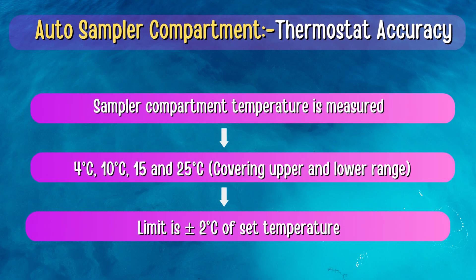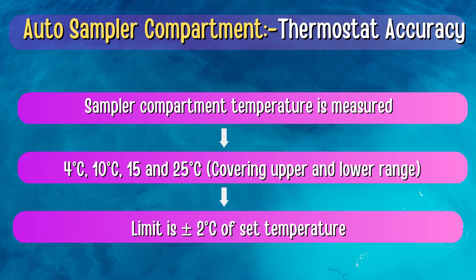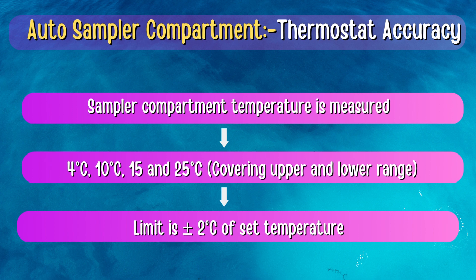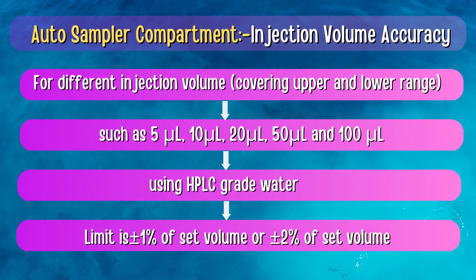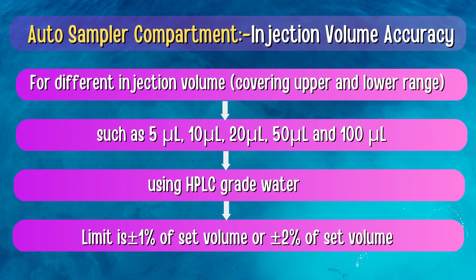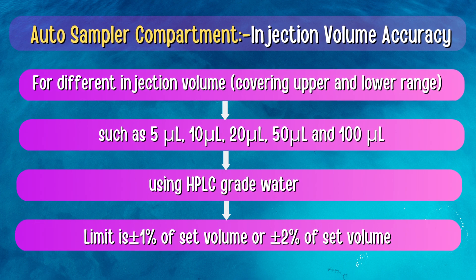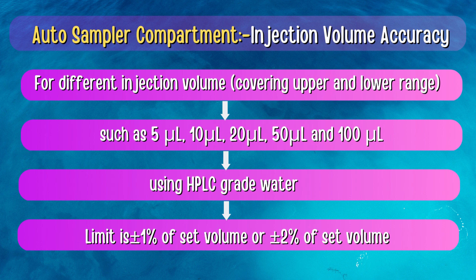For the Auto Sampler Compartment, Thermostat Accuracy is performed by measuring the sampler compartment temperature at 4°C, 10°C, 15°C, and 25°C. The limit is ±2°C of the set temperature. For Injection Volume Accuracy, different injection volumes are tested such as 5 µL, 10 µL, 20 µL, 50 µL, and 100 µL using HPLC grade water. The limit is ±1% or ±2% of the set volume, depending upon the make of the HPLC.